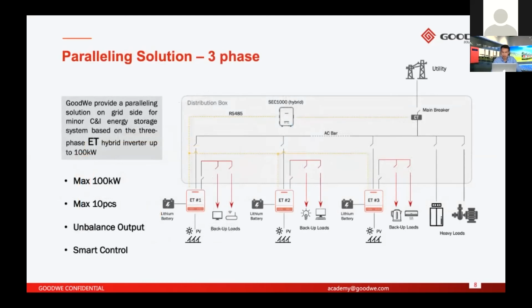And this one is the paralleling system. For paralleling systems, we support this function only on the ET hybrid inverter. ET is our three-phase hybrid inverter that uses high voltage batteries. Another thing is that this paralleling is only on the on-grid side. From the diagram, you can see each ET connects lithium batteries separately, connects PV separately, and connects backup load separately. Only the on-grid side is connected together.